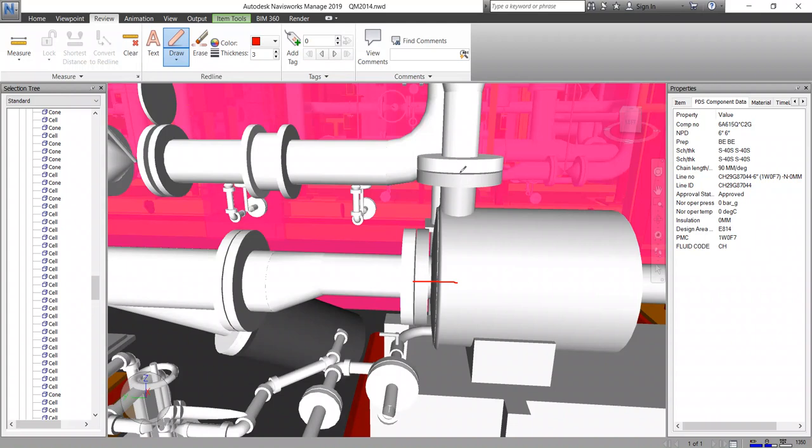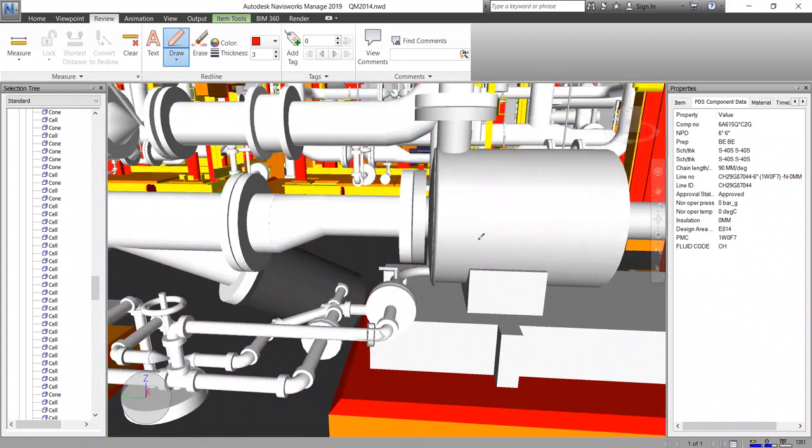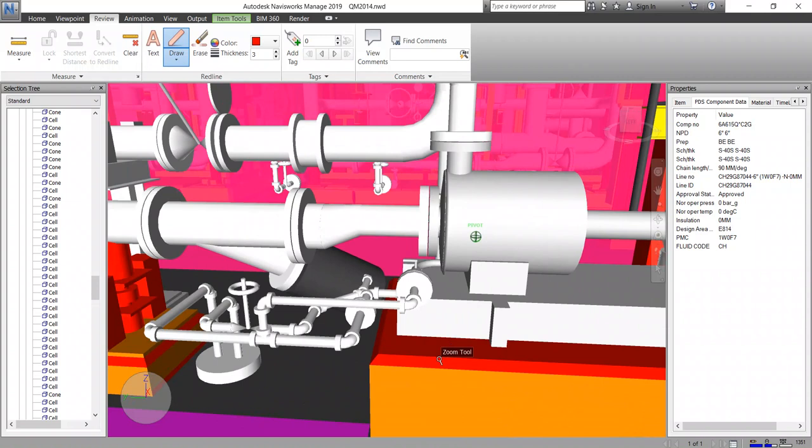Like this, and if you want to model the discharge, you have to go up, or if you don't want to model, you have to go like this up to the center line of discharge, okay, and then go downwards where it is getting bolted. You see, I will show you the vendor drawing. So based on the vendor drawing, we need to model. Okay, or if you want to model up to the bolt ends, here you can stop, or if you want to go up to foundation, you can anchor here.